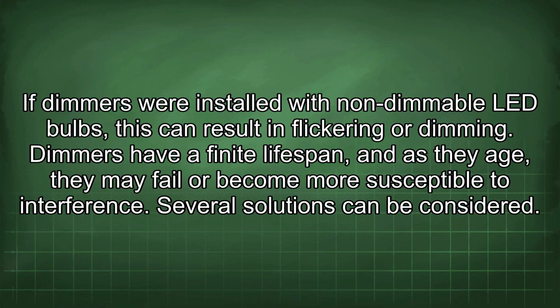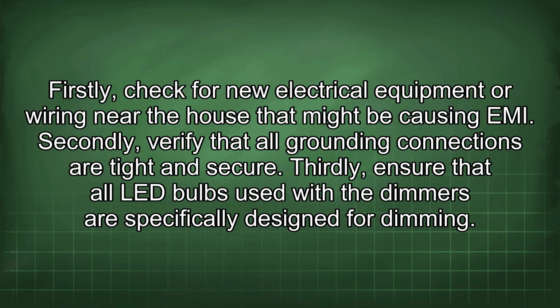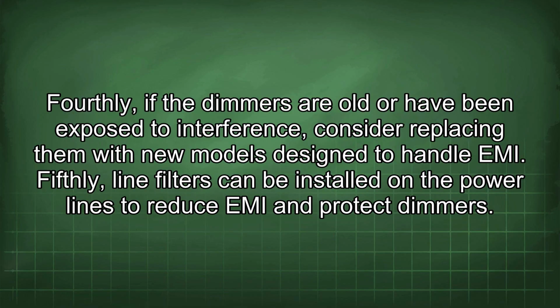Several solutions can be considered. Firstly, check for new electrical equipment or wiring near the house that might be causing EMI. Secondly, verify that all grounding connections are tight and secure. Thirdly, ensure that all LED bulbs used with the dimmers are specifically designed for dimming. Fourthly, if the dimmers are old or have been exposed to interference, consider replacing them with new models designed to handle EMI. Fifthly, line filters can be installed on the power lines to reduce EMI and protect dimmers.